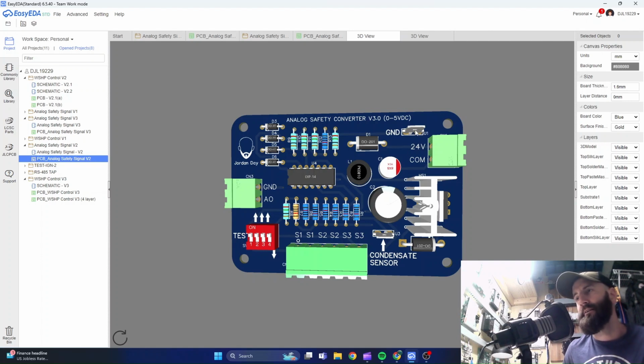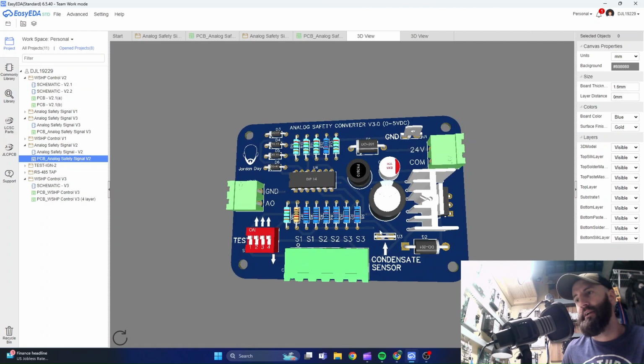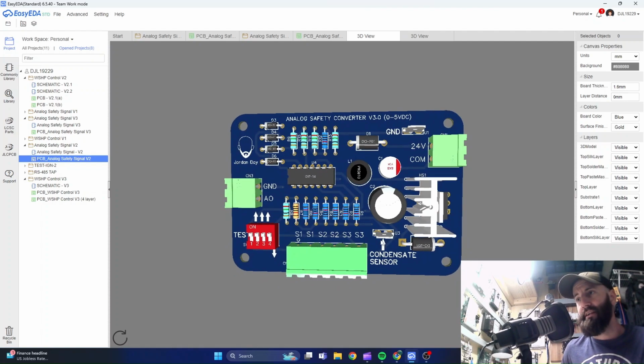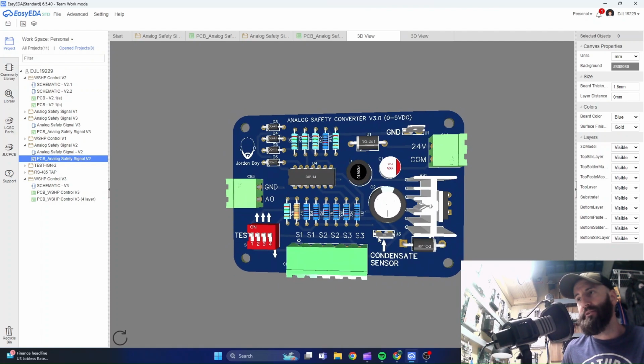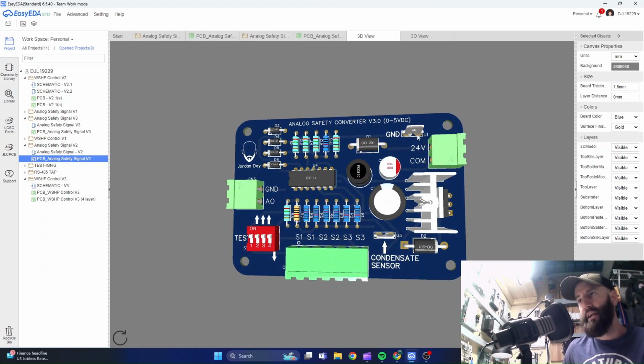And so you would want one of your probes to be at ground or equal potential if you don't have a metallic condensate pan, like a stainless condensate pan. If you do, then you could just take this ground to the chassis anywhere. And this will usually work just having a single probe dangled over the condensate drain. But if you have a plastic pan in this application, what you want to do is take this to the chassis and also take this to one of the probes.